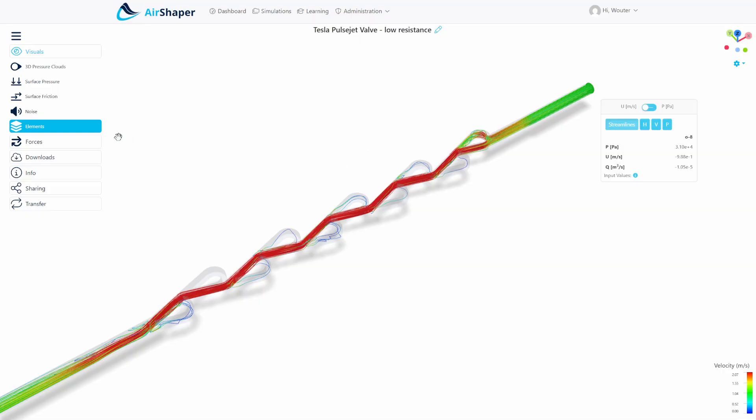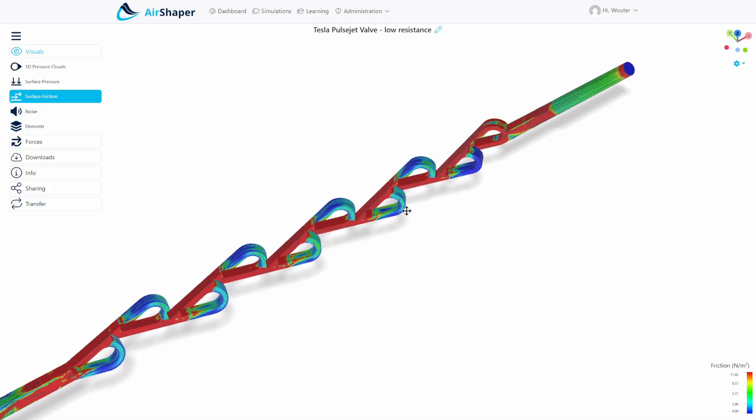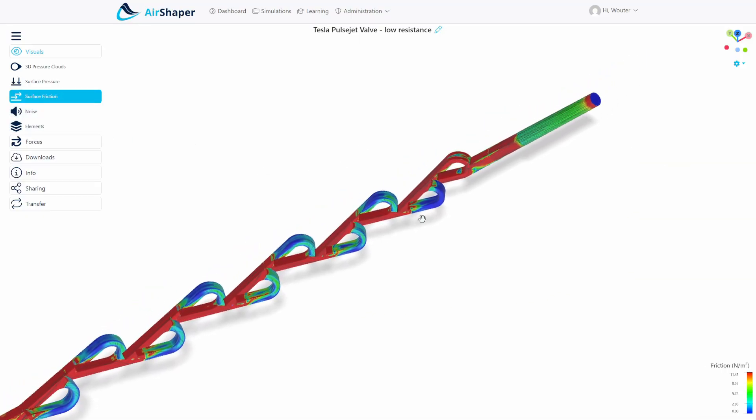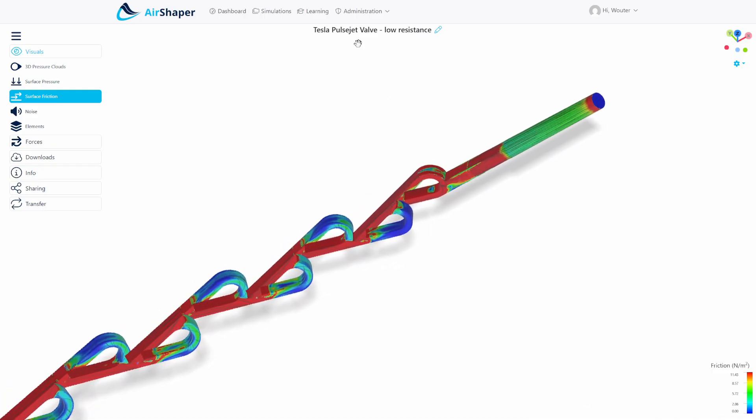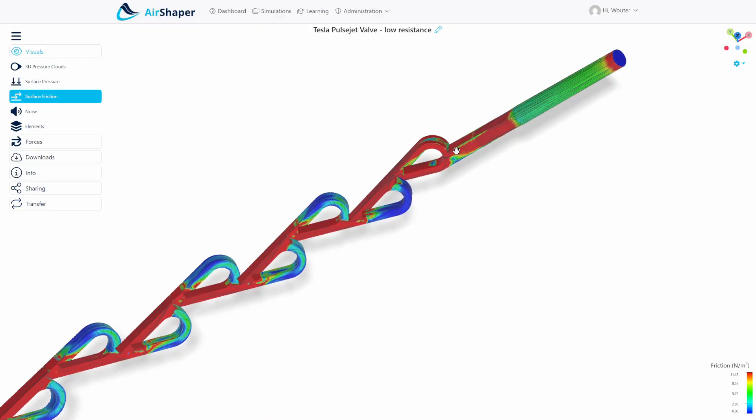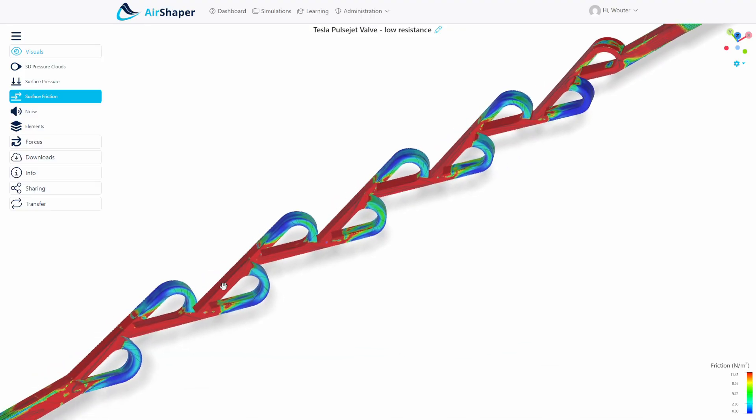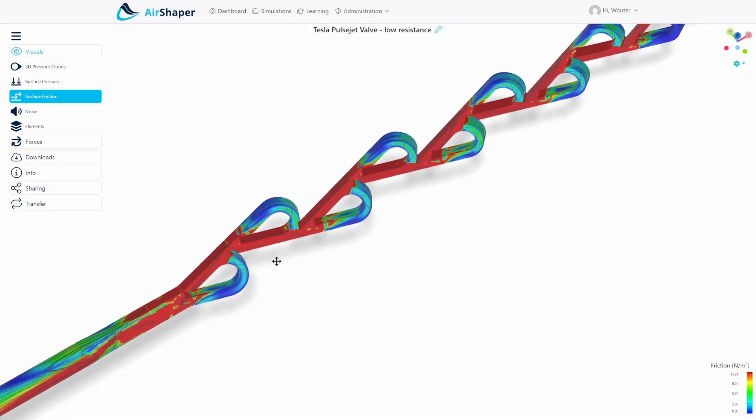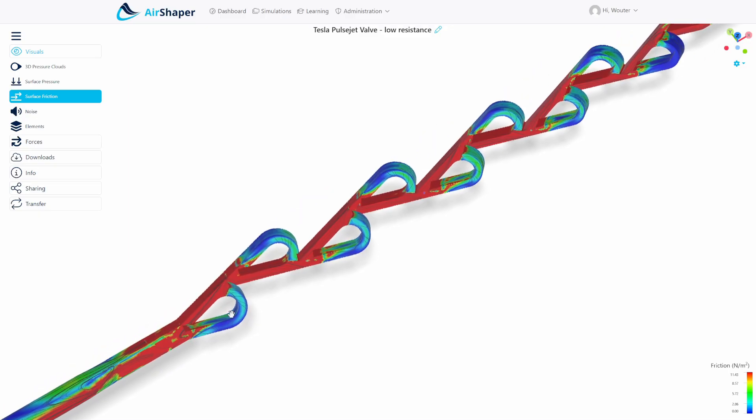We can also dive in to see what is happening with the friction patterns. In the low resistance situation, you can see the red areas where the liquid at the beginning still goes into this corner, but then the mainstream is just via the center. That's where you have wall friction, but the bends are not being used and are not obstructing the flow a lot. You have a bit of turbulence and flow separation, but other than that, the pressure drop is quite low.